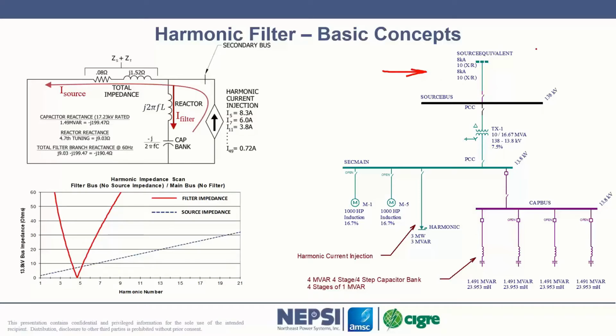I have a source equivalent. This represents the utility power system, what's feeding an industrial facility. I have a point of common coupling. This is a common thing for IEEE 519, is we need to determine what the current distortion and voltage distortion is here. And the filters down at this point must limit the voltage and current up here. And these are the standards that we typically follow in North and oftentimes also in South America.